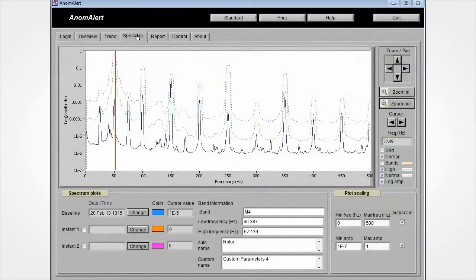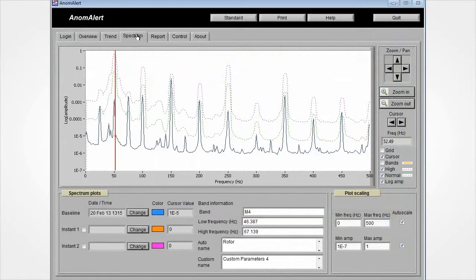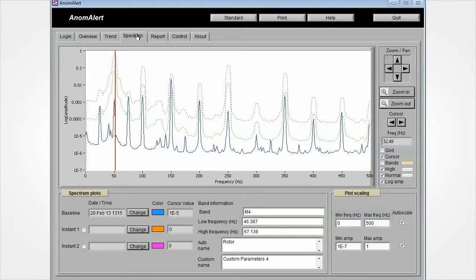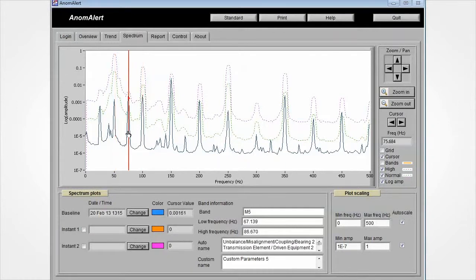The spectrum page in Anomalert software shows the PSD plot, or the Power Spectrum Density plot. From this plot, mechanical faults are determined and derived. The various frequency bands are usually indicative of different mechanical problems.